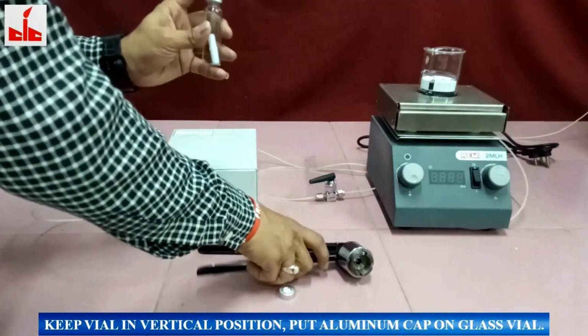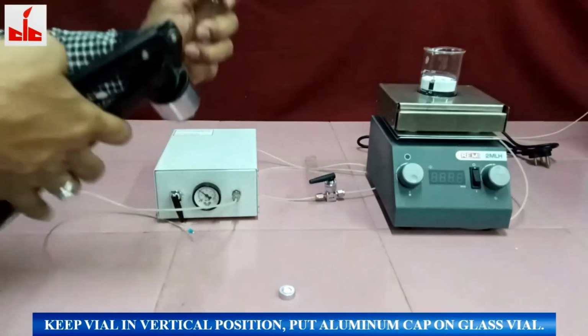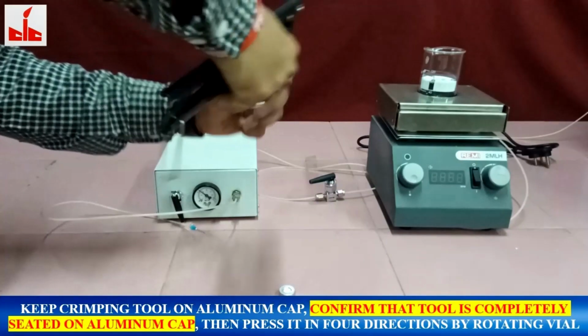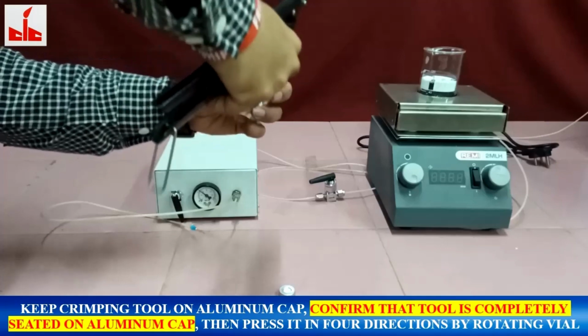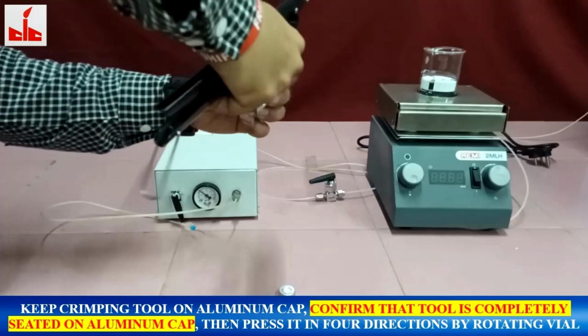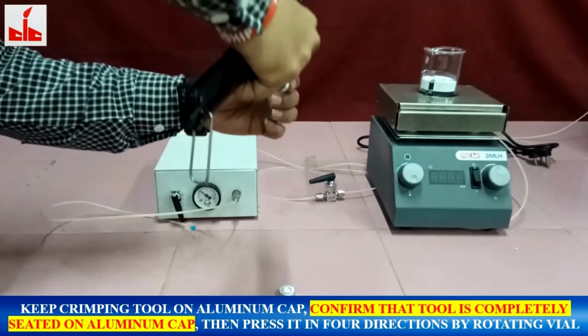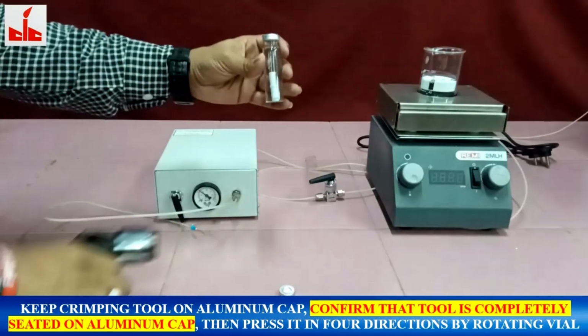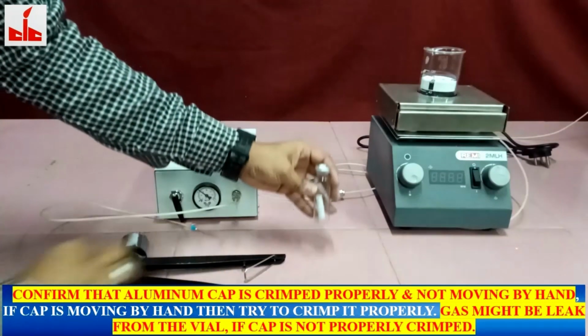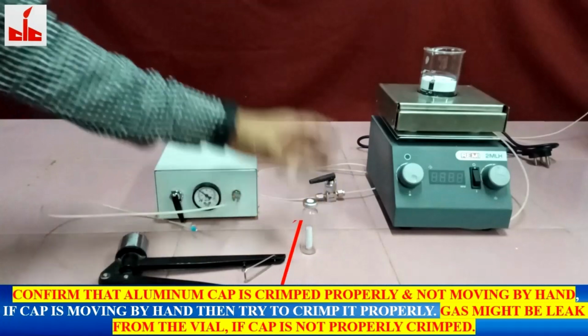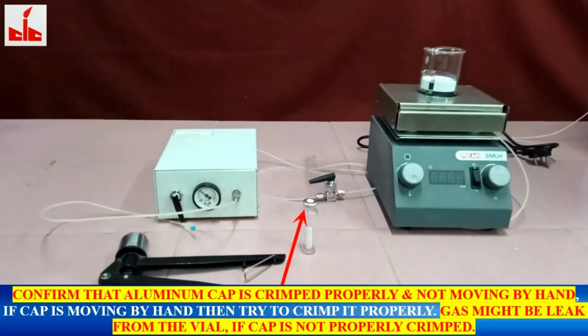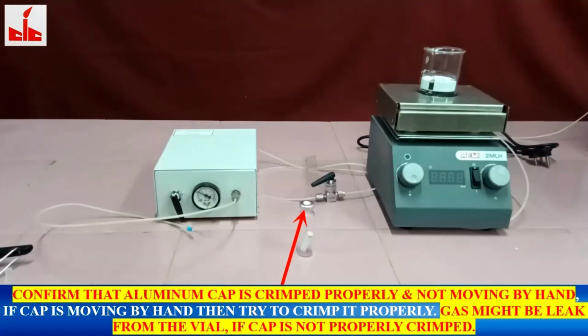Keep the vial in vertical position and put the aluminum cap on the glass vial. Keep the crimping tool on the aluminum cap, confirm that the tool is completely seated on the aluminum cap, then press it in 4 directions by rotating the vial. Confirm that the aluminum cap is crimped properly and not moving by hand. If the cap is moving by hand, then try to crimp it properly. Gas might leak from the vial if the cap is not properly crimped.